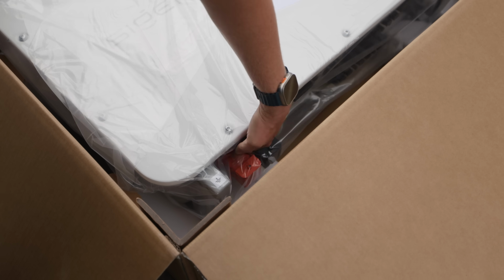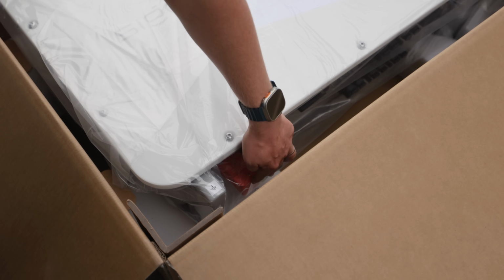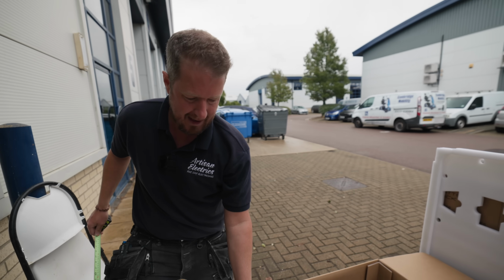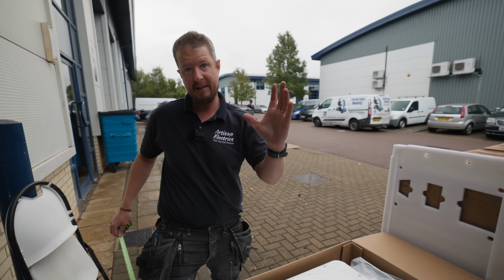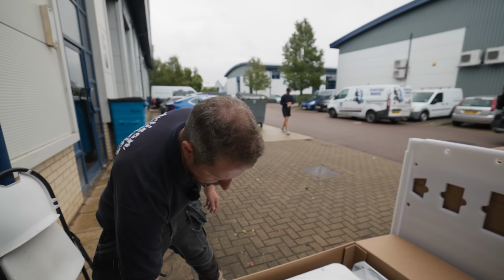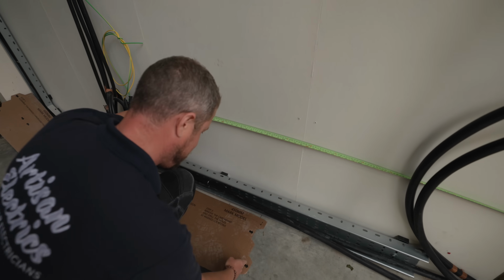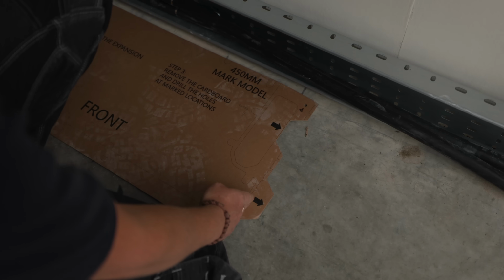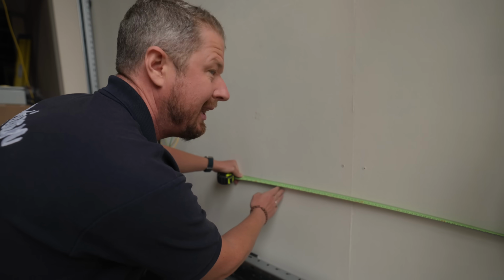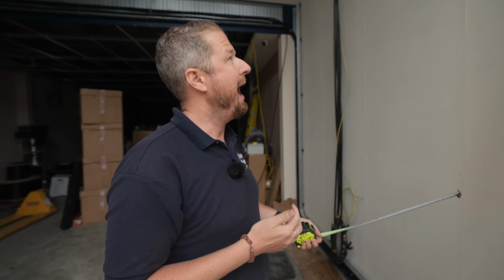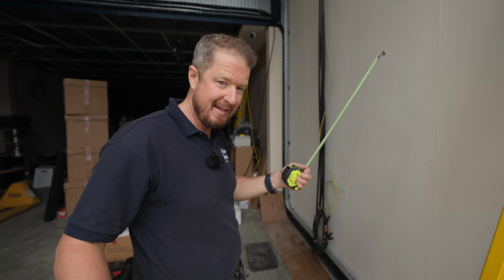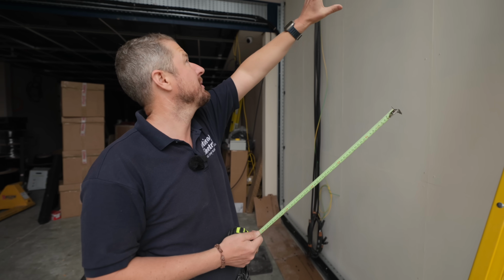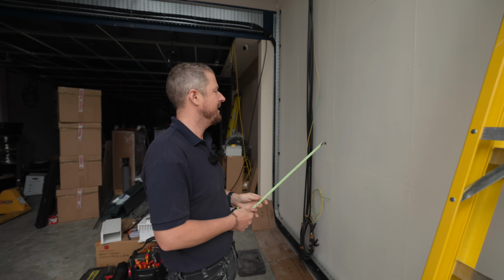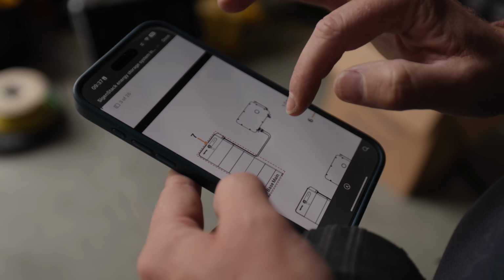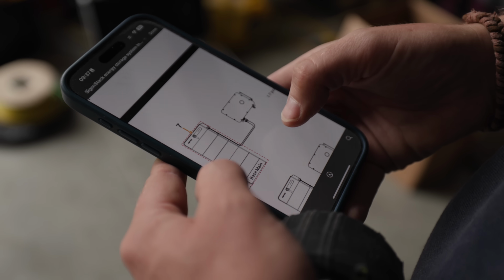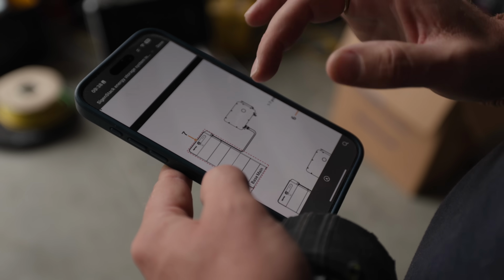So you see those orange or red and black terminals, that's where the battery cables drop out. So what we want is the DC cables from there to drop out nicely into the first stack of the batteries. So we've got 1.1 meter space, and the side of the batteries is going to be here. So we've got a little bit of a problem there. We've got our AC cables that have got to go in on the right hand side of the inverter. So really for that purpose we need the inverter to be over to this side slightly. So this is how it shows it on the diagram, with the inverter to the side of the batteries. But obviously we're not going to be able to do that because we've not got enough width.